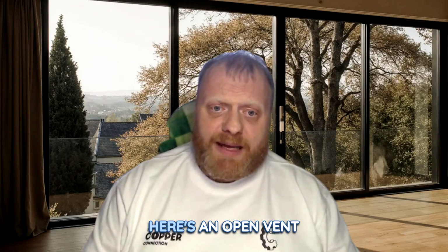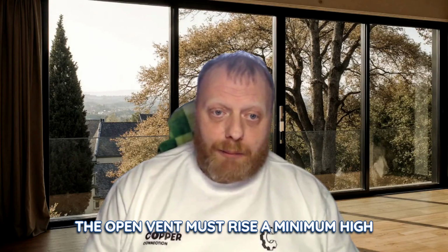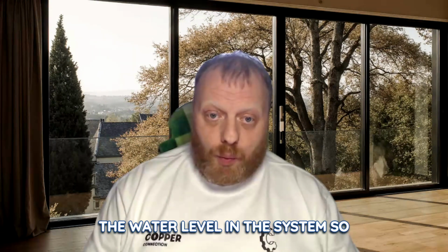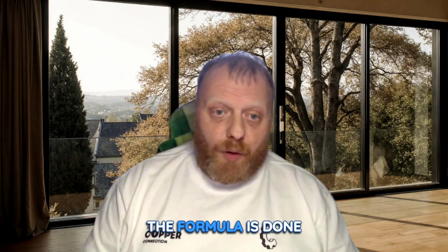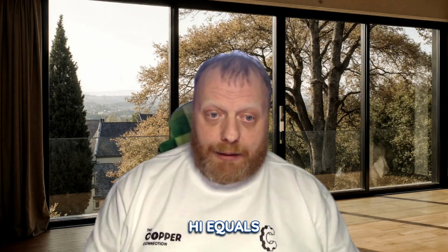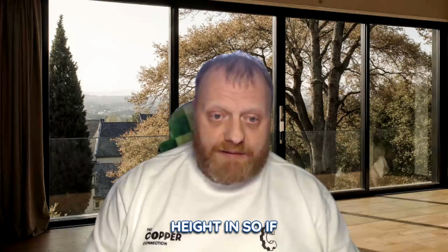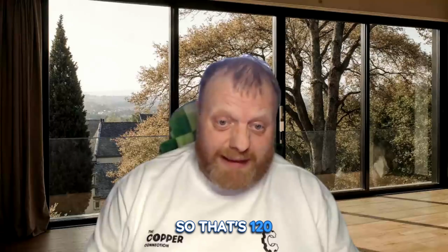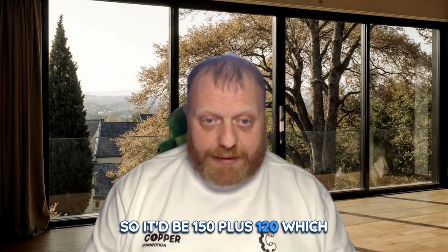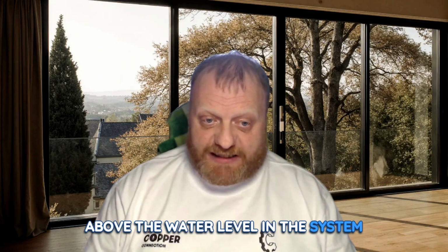There's a calculation to remember here: open vent height. The open vent must rise a minimum height above the water level in the system. The formula is vent height equals 150 millimeters plus 40 millimeters per meter of height. So if the system height is 3 meters, it'd be 150 millimeters plus 40 millimeters times 3, so that's 120. So it'd be 150 plus the 120, which gives us 270 millimeters. So the vent pipe rise must be at least 270 millimeters above the water level in the system.